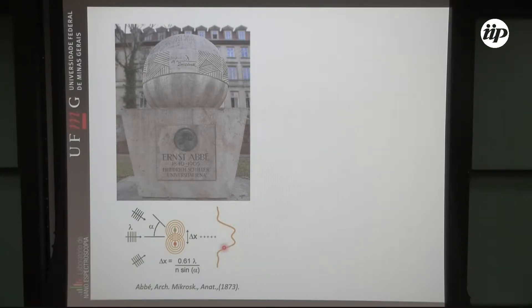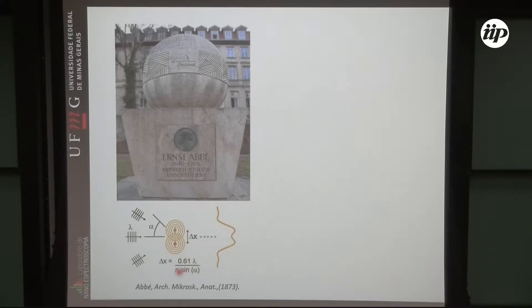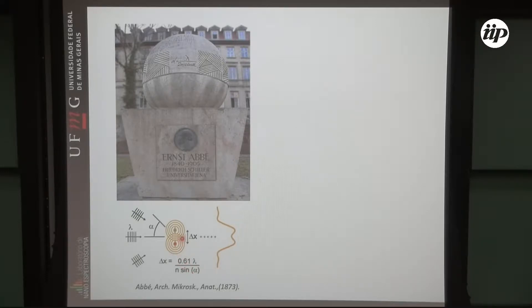This is a very strong statement about spatial resolution: you cannot resolve two point sources which are smaller than this number here — 0.61 lambda over the NA. This is the numerical aperture of your objective lens, equal to sin alpha, where alpha is the aperture angle. If you open more and more, you squeeze this, but you cannot go beyond something around half lambda.